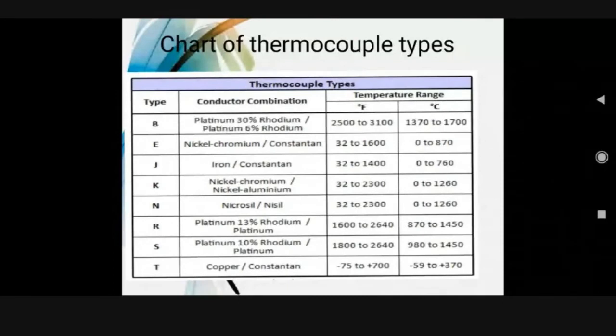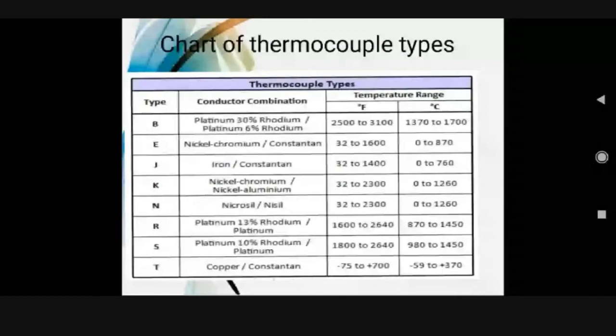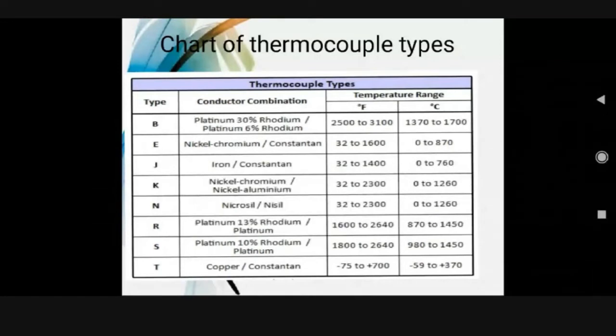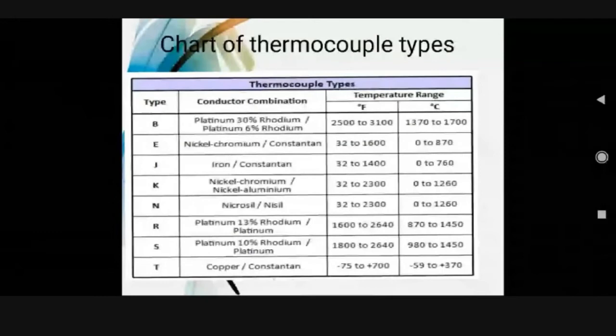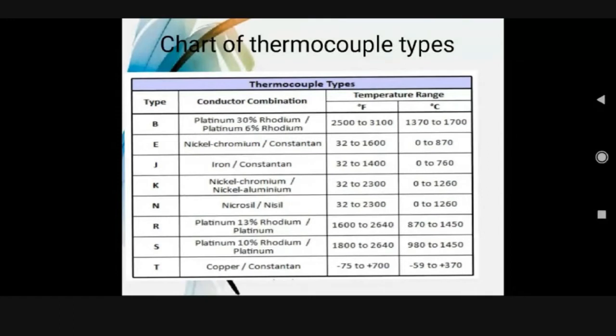Type J, iron constantan, 32 to 1400 Fahrenheit, 0 to 760 degrees Celsius. Type K, nickel chromium, nickel aluminium, 32 to 2300 Fahrenheit and 0 to 1260 degrees Celsius. Type N, Nicrosil, Nisil, 32 to 2300 Fahrenheit, 0 to 1260 degrees Celsius.